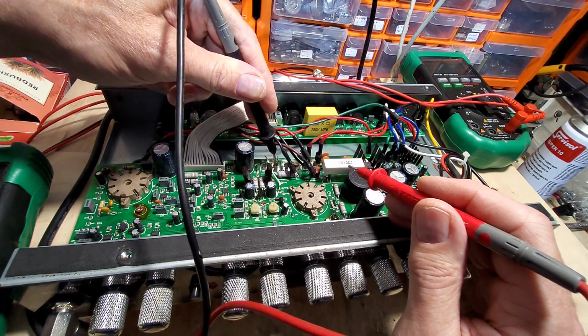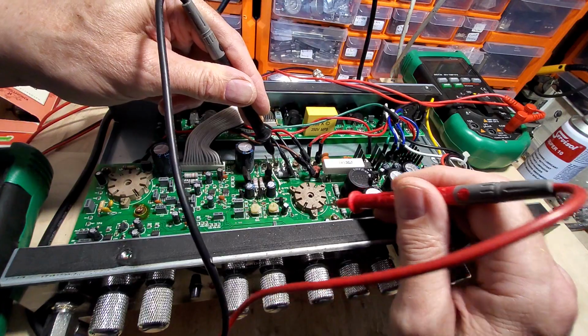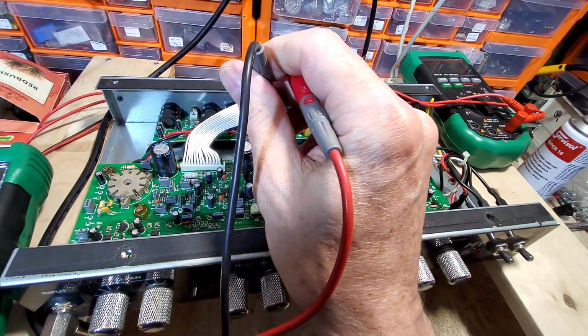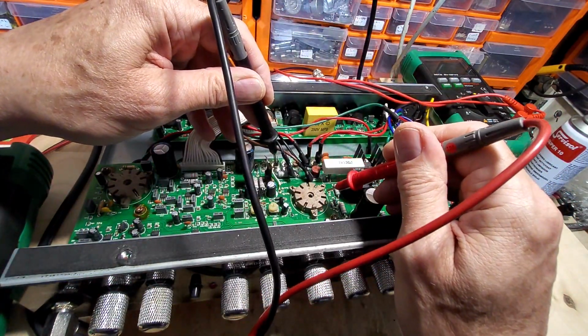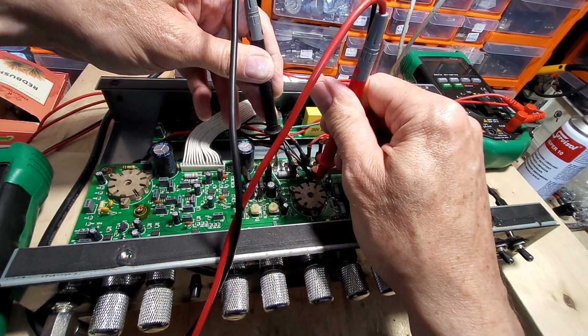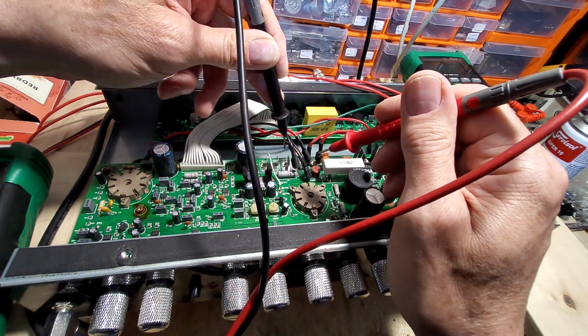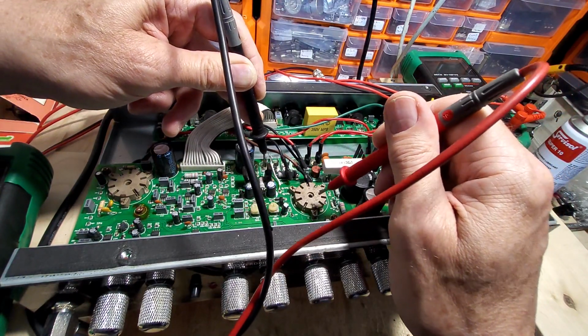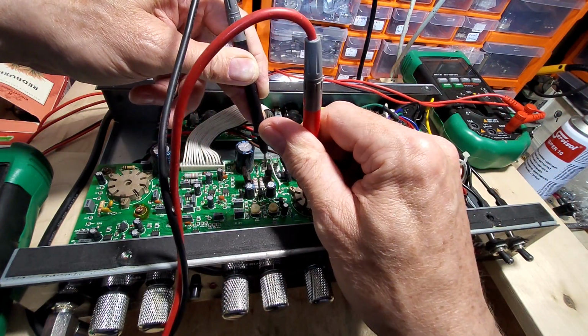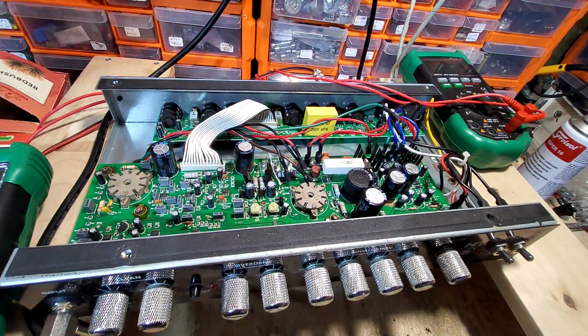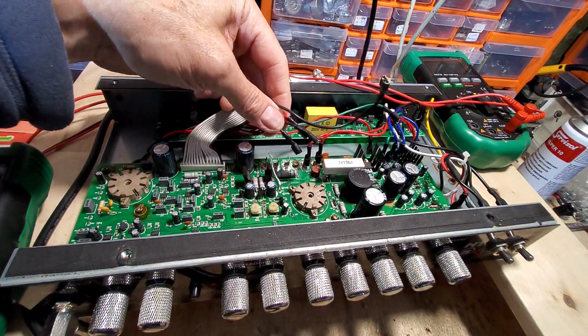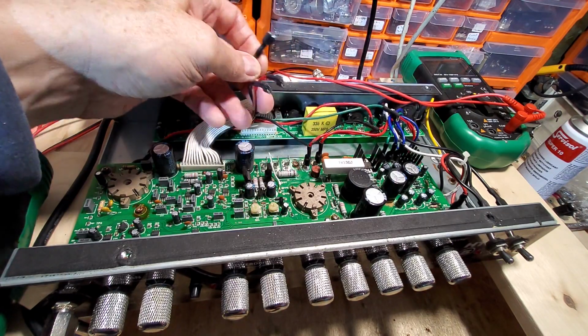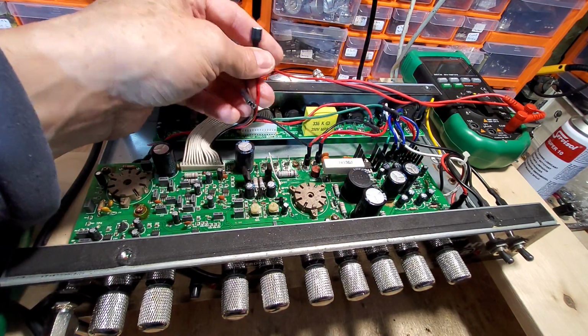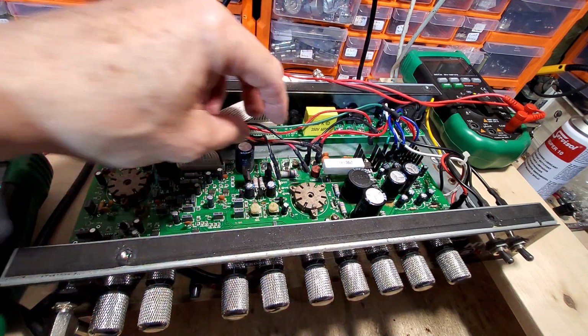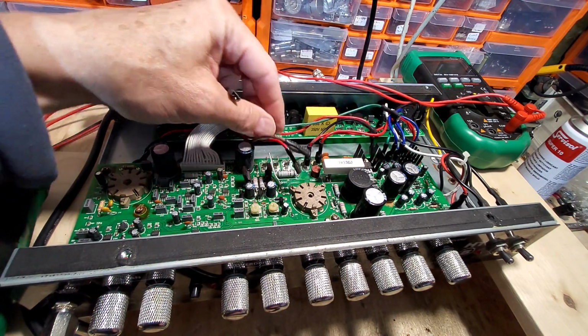So if I go to red and I go to pin 1, oh sorry, wait, yep, nothing, pin 6, yeah, I've got continuity there. And if I go to the black connection, I get, yep, continuity. So definitely without question, brown is the center tap on there and not red. Always pays to check. So we need the black and the red wire to do this turns ratio test.